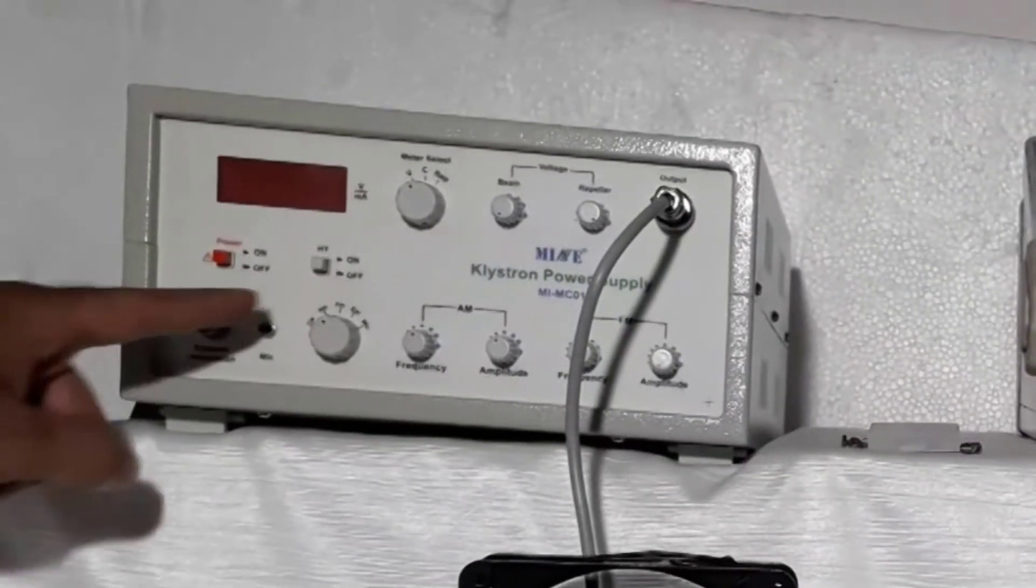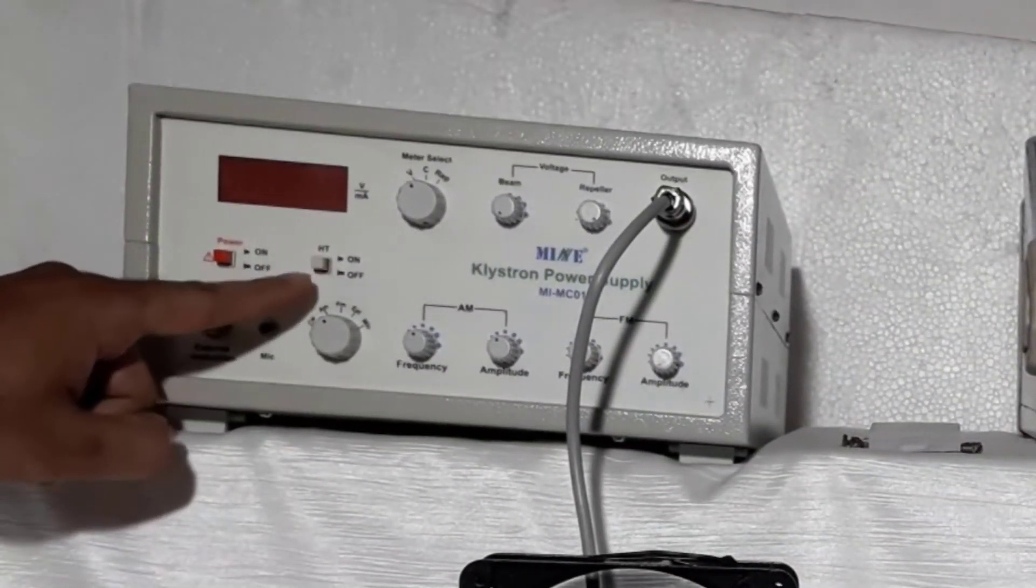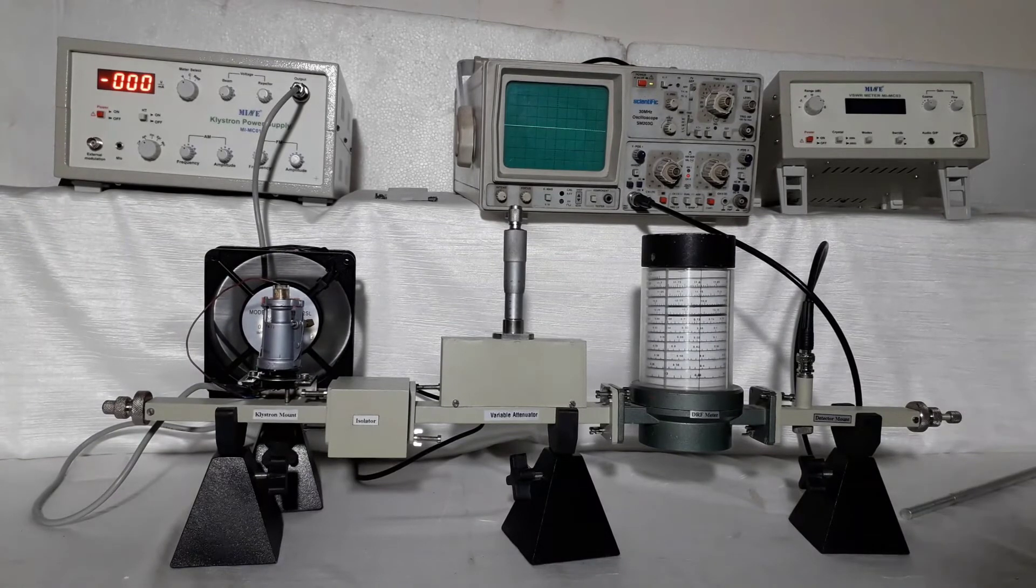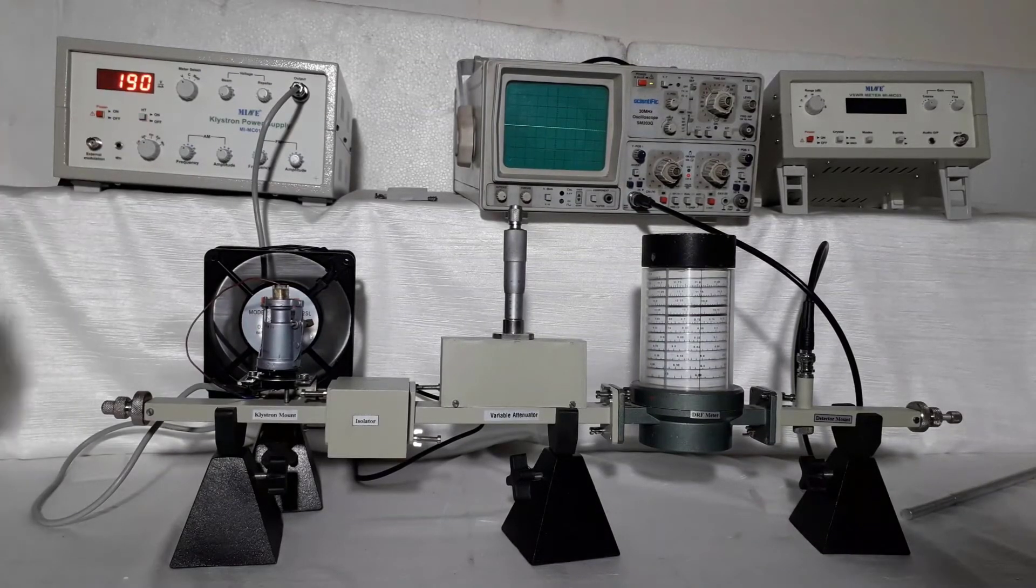Ensure that HT is at off position. Now power on klystron power supply and CRO. Now keep HT is at on position.